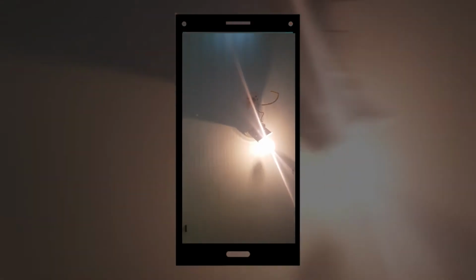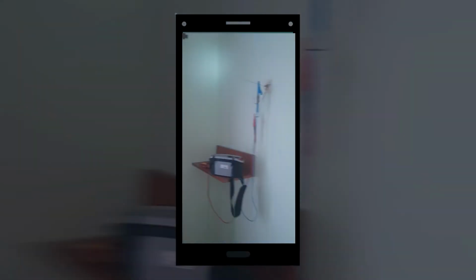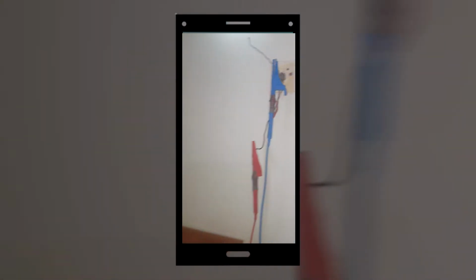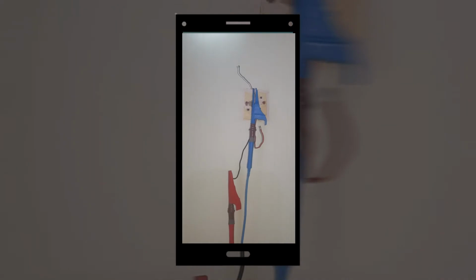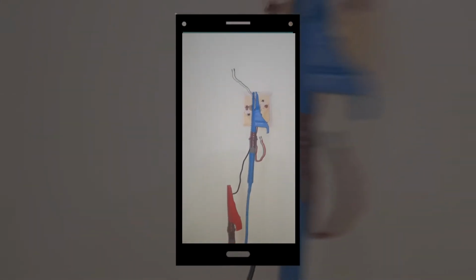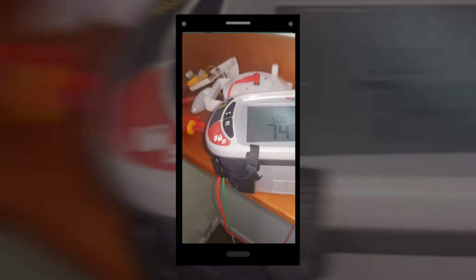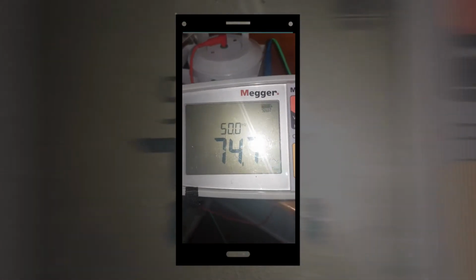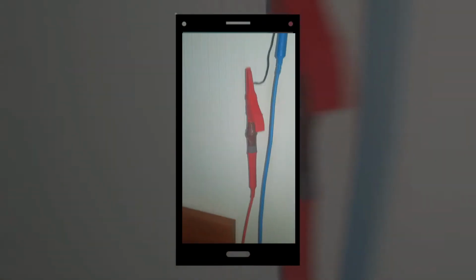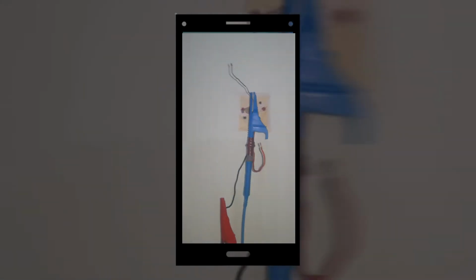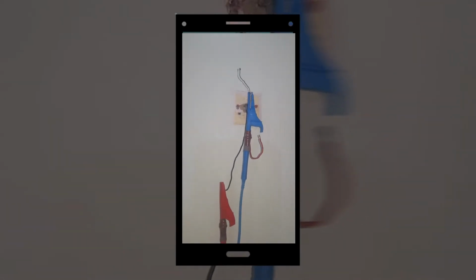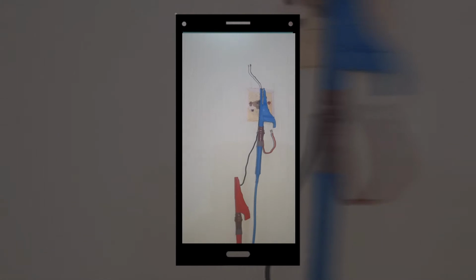I've been called out to some wall lights that weren't working properly. One of them in particular kept blowing bulbs, and when I actually checked the light fitting, which is metal, I ended up getting 75 volts from neutral to earth, which is obviously bad news on a metal light fitting. So it's time to do some investigation work.